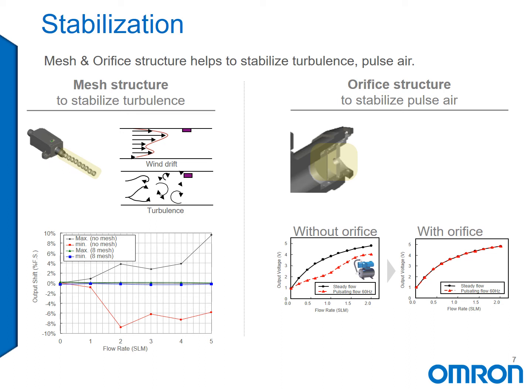The orifice structure at either end of the sensor helps to stabilize the pulse air. Without the orifice, we have a very unsteady flow and could potentially compromise the data that's being read by the sensor or the airflow supply into the rest of the system.